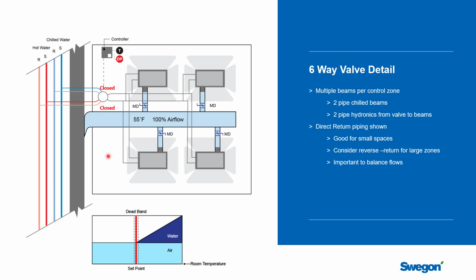If you have that image of a classroom in your mind, and you think about a space that's 1,000 square feet with 6 beams in it, there's a fair amount of piping going on in that room up above the ceiling. There's a lot of joints. There's a lot of labor in here. You're going to cut that labor and material in half within the classroom to get it back over to the valve. And in addition, you get increased capacity from the beams, because every tube in the beam can be in heating, or every tube in that beam can be in cooling. So you just get more capacity from the beams. Nice solution when you can do it, and it helps with managing your capital budget.